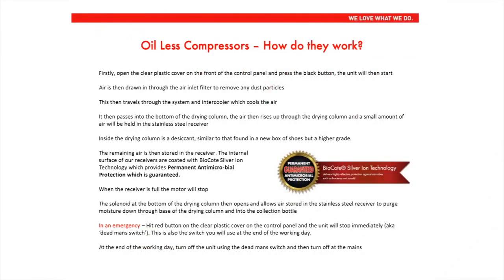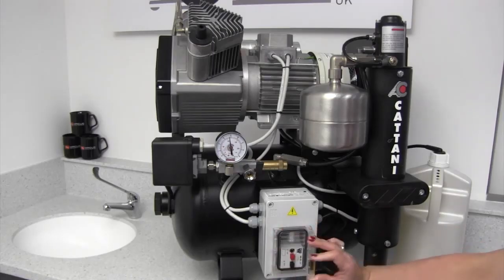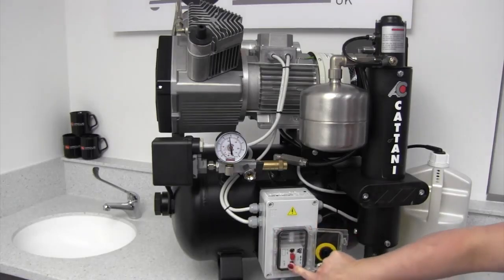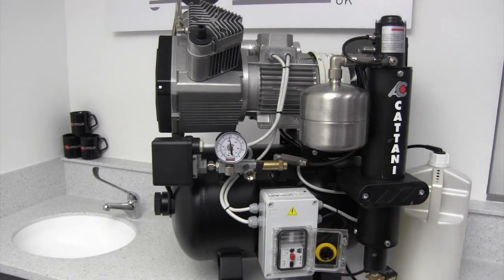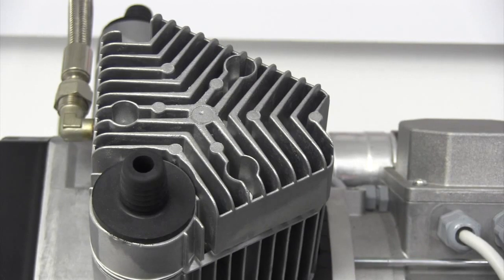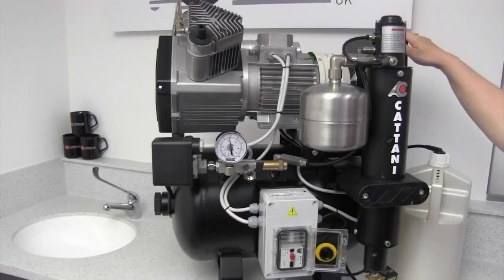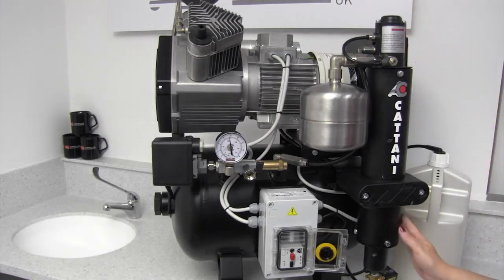Oilless compressors, how do they work? Firstly, open the clear plastic cover on the front of the control panel and press the black button. The unit will then start. Air is then drawn in through the air inlet filters to remove any dust particles. This then travels through the system and intercooler, which cools the air. It then passes into the bottom of the drying column.